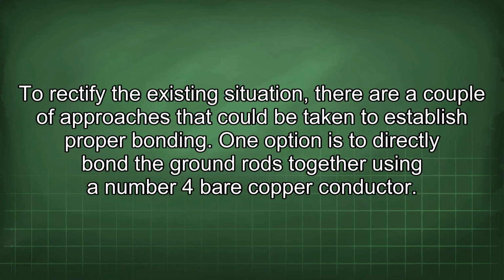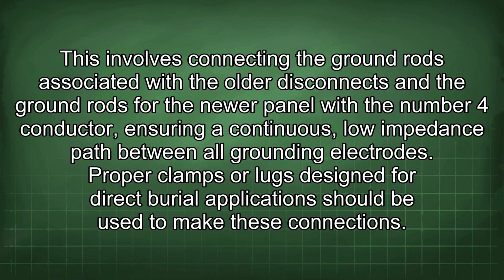To rectify the existing situation, there are a couple of approaches that could be taken to establish proper bonding. One option is to directly bond the ground rods together using a number 4 bare copper conductor. This involves connecting the ground rods associated with the older disconnects and the ground rods for the newer panel with the number 4 conductor, ensuring a continuous, low impedance path between all grounding electrodes. Proper clamps or lugs designed for direct burial application should be used to make these connections.